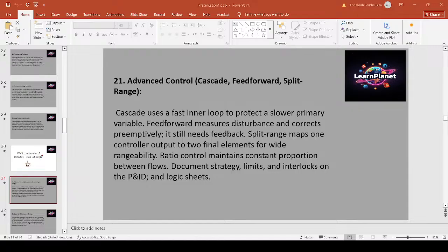Cascade control nests a fast inner loop, for example valve position or flow, under a slower outer loop to speed up disturbance rejection. Feedforward uses a measured disturbance like inlet flow to pre-correct the controller, reducing dependence on feedback, but it still needs feedback for offset. Split range lets one controller drive two final elements. Example: two valves across different ranges for wide capacity. Ratio control locks two flows together, like fuel to air or chemical dosing. Example: implement cascade level control where the slave loop controls the inlet flow valve and the master loop adjusts setpoints based on downstream demand.